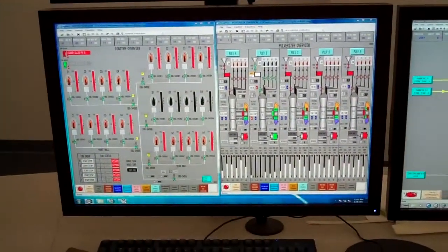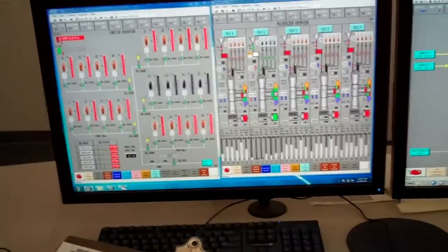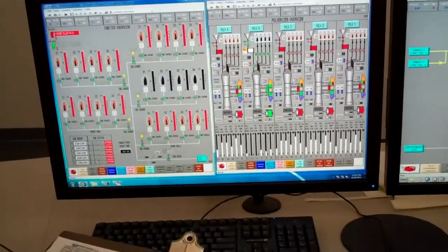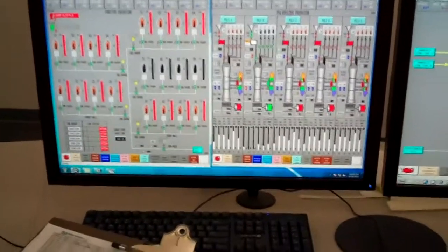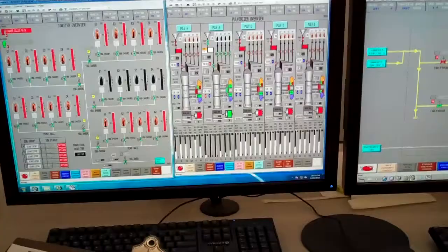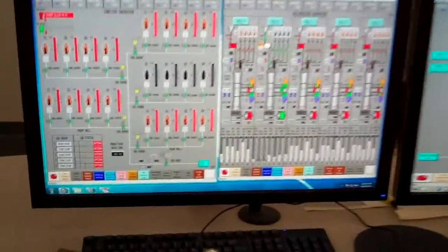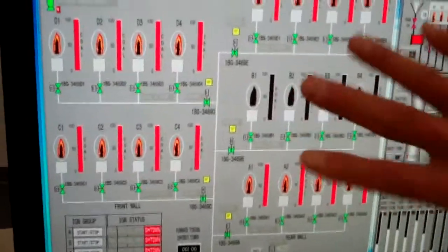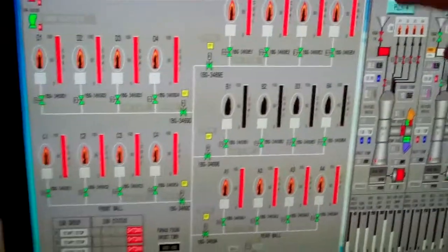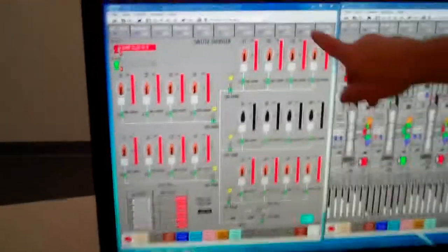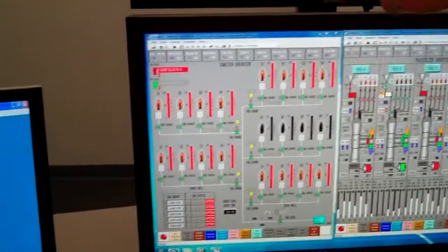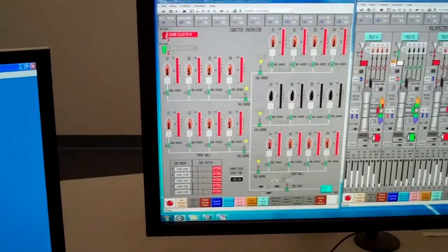These are the igniters. These are your flame scanners that are picking up on the pulverizers that are running. So you can see the flame scanners on B right here. Those are all black because that mill is shut off. Every one of these other mills is on. And these are your flame scanner intensities. If these start dropping out, then you could lose that mill.